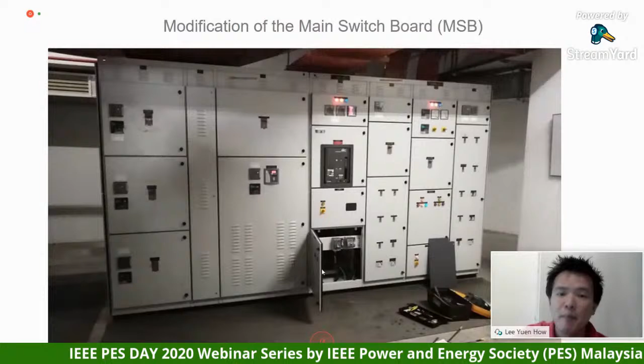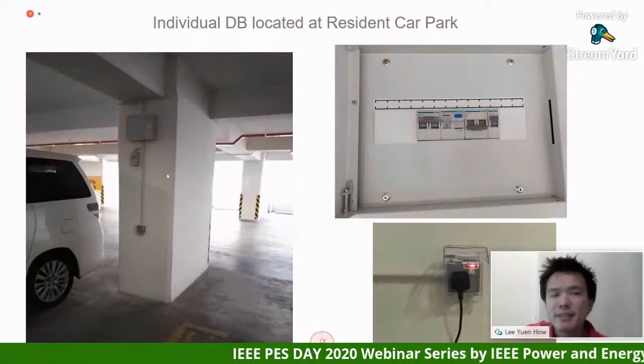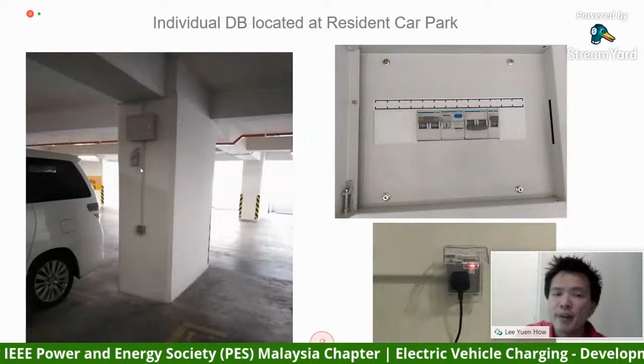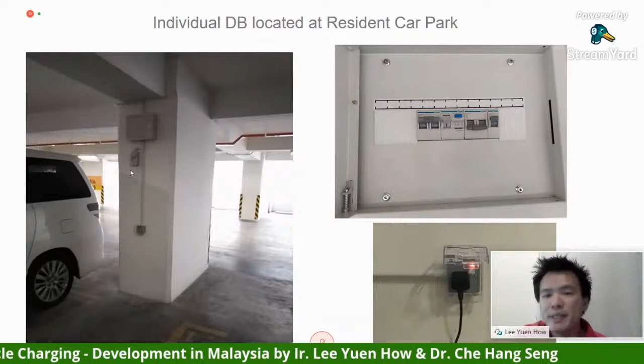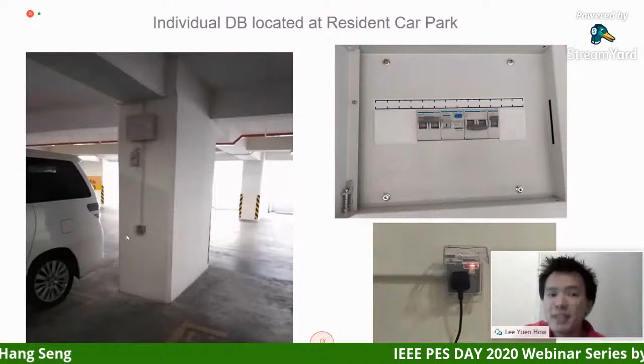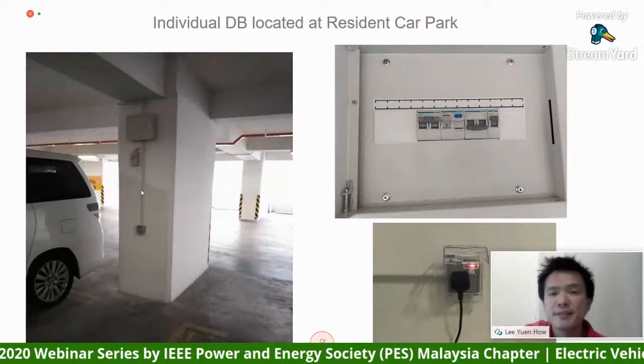Each residence will be provided with a DB with an individual RCCB for protection, so they do not disturb the upstream. For this project, each resident is provided with at least 7 kilowatts of power, with an isolator and a socket for installing a charger. As you know, condominiums and apartments now have 2 to 3 car park bays per unit, so this facility can cater for simultaneous charging of at least 2 to 3 cars.